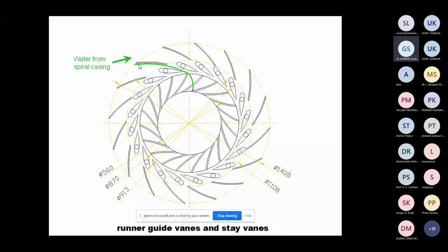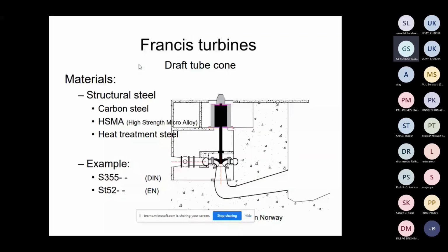This is like this. Then the draft tube. I told you about the draft tube cone. The bottom of the turbine end and the starting point of the draft tube are connected by some patches of carbon steel. This is called my draft tube cone. That can be dismantled, from this point to this point. Then your machine can be held by the jacking system of the unit.